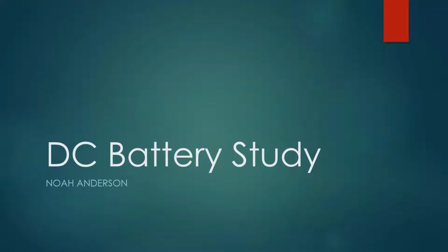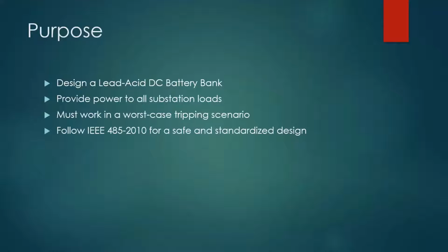Hi, my name is Noah Anderson, and I'll be going over the DC battery study. The purpose of the DC battery study was to design a lead-acid DC battery bank to provide power to the substation in the case that it's lost. It must provide power to all of the DC substation loads and be able to work in a worst-case tripping scenario, all while following IEEE standard 485-2010.